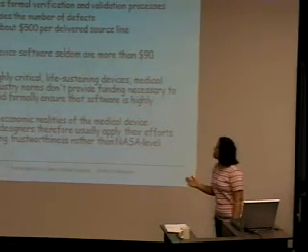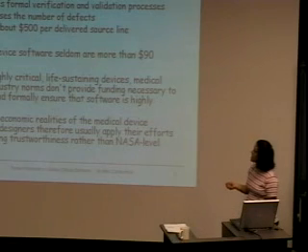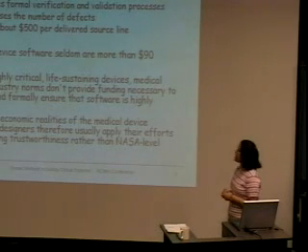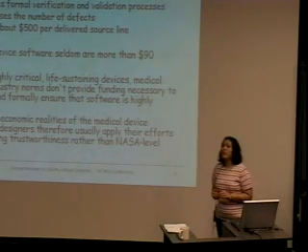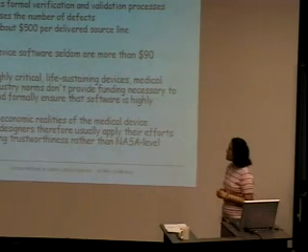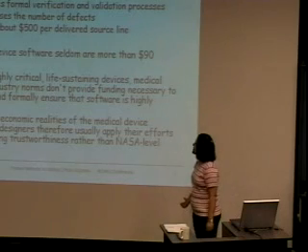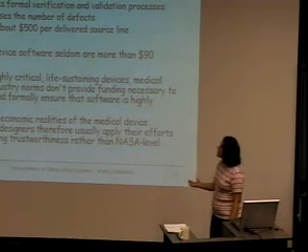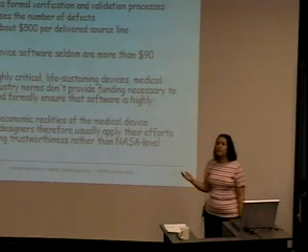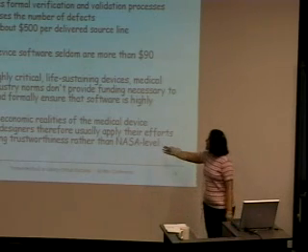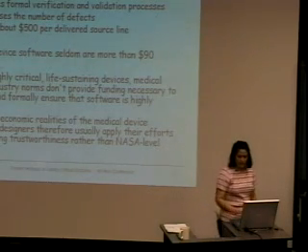Even in highly critical, life-sustaining medical devices, the industry does not support enough funding for development and the formal specification and formal verification of the software. Given these realities, the medical device industry and developers usually tend to go for trustworthiness instead of high reliability or NASA-level reliability.